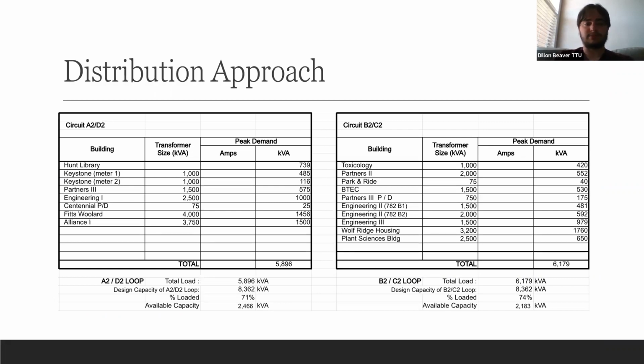We created 2 loop systems. We have an A2 and D2 loop system, which has a total load of 5,896 kVA. Design capacity of this is 8,362 kVA with a total load percentage of 71%, so remaining available capacity would be about 2,466 kVA on the first loop. Total load on the second loop is 6,179 kVA, design capacity is 8,362, so the overall percentage load is 74%, with available remaining capacity of 2,183 kVA.